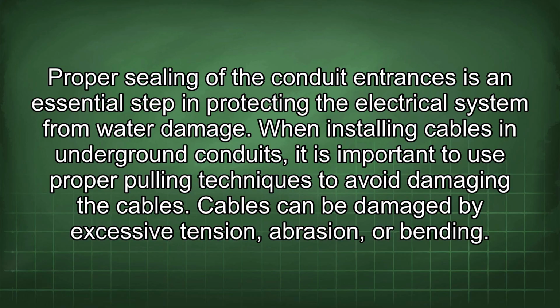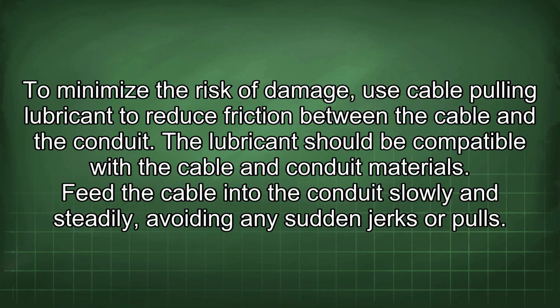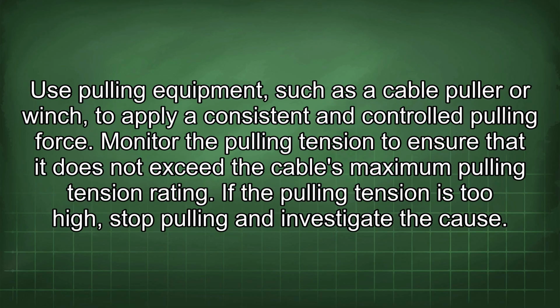When installing cables in underground conduits, it is important to use proper pulling techniques to avoid damaging the cables. Cables can be damaged by excessive tension, abrasion, or bending. To minimize the risk of damage, use cable pulling lubricant to reduce friction between the cable and the conduit. The lubricant should be compatible with the cable and conduit materials. Feed the cable into the conduit slowly and steadily, avoiding any sudden jerks or pulls. Use pulling equipment, such as a cable puller or winch, to apply a consistent and controlled pulling force.